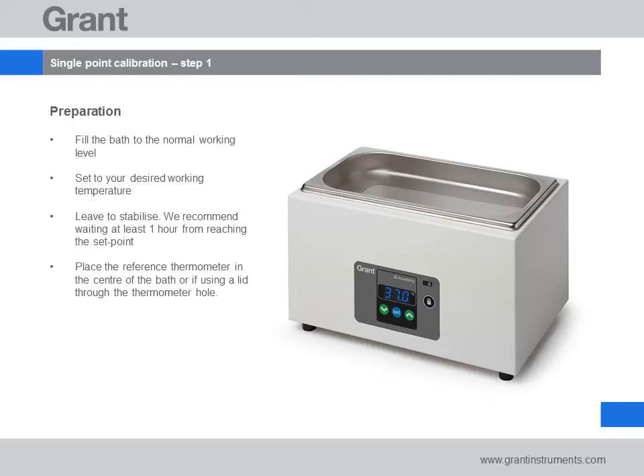The first steps in performing a single point calibration involve filling the bath to your normal working depth, and then setting the bath to the working temperature you'd routinely use. We'd recommend leaving the bath to stabilise at the set temperature for at least an hour. After the temperature has stabilised, place the reference thermometer either in the centre of the bath or, if using a lid, through the thermometer hole.